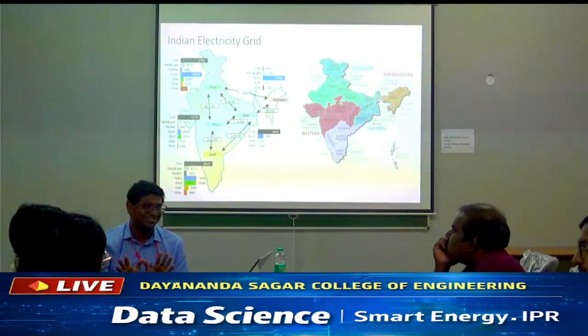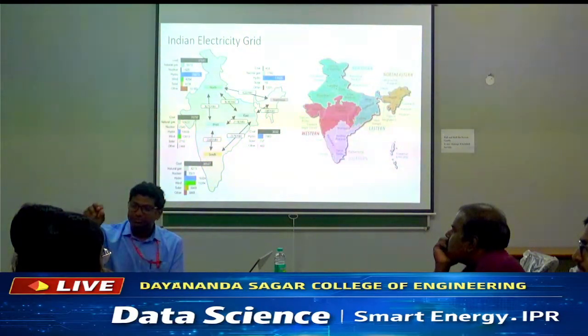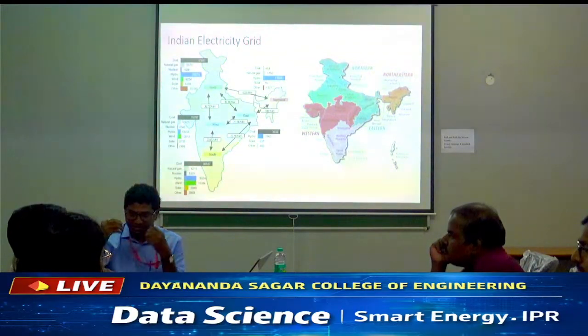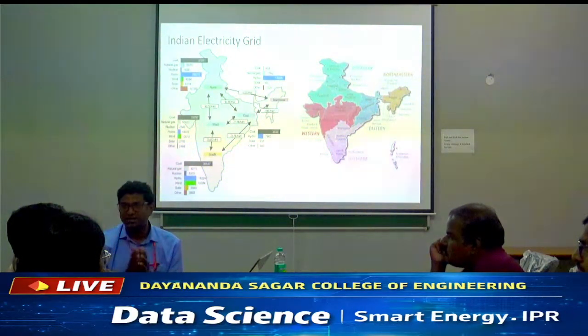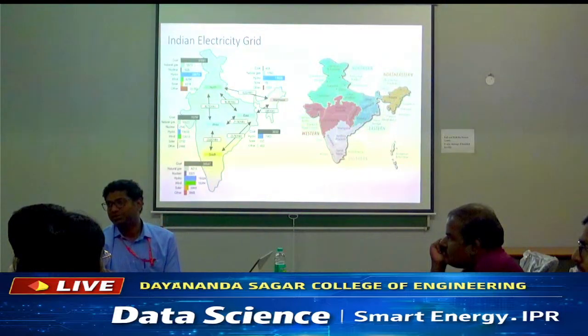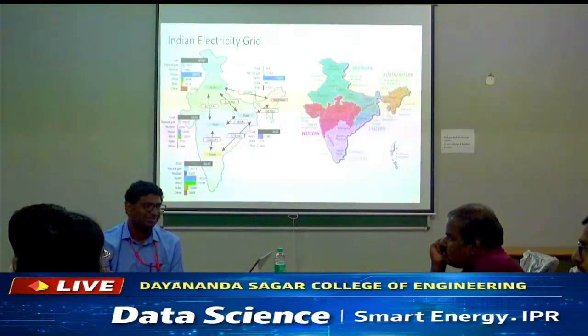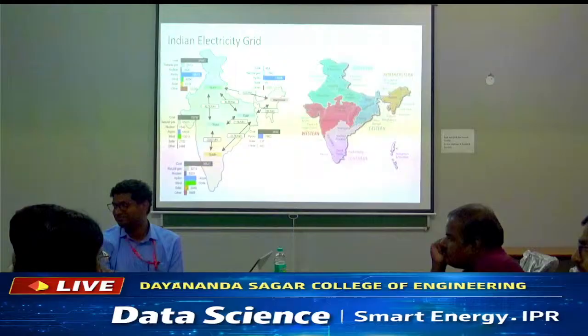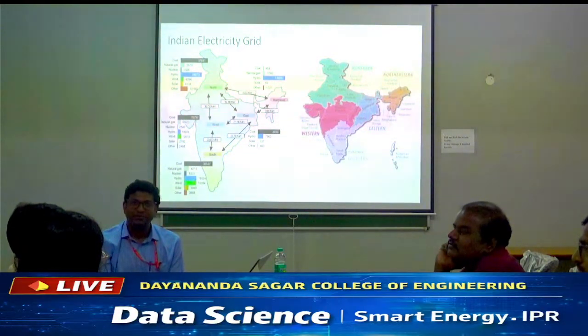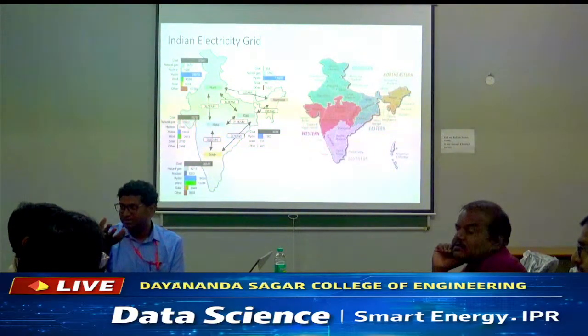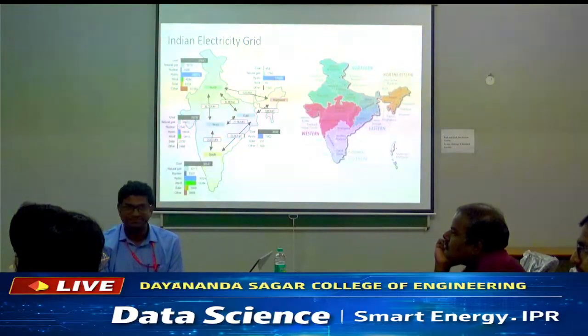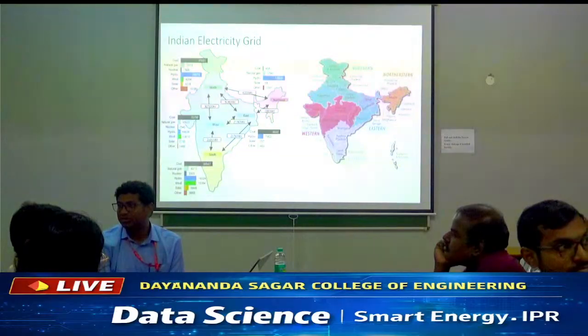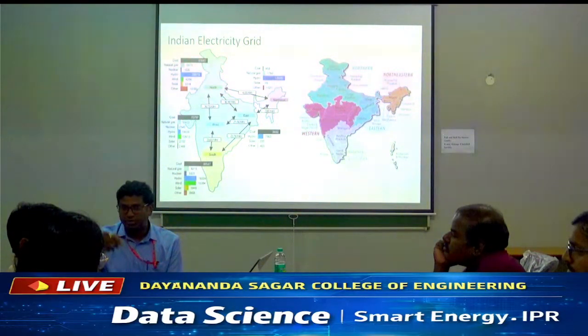Power cannot be pumped. Even if you simply connect to the grid, you cannot pump power from your system. Why? Because according to theory, the inverter cannot produce reactive power. But I also know that without reactive power, real power cannot flow. So if you have an inverter connected to the grid, can you pump the power? No, you cannot. For that, you need some amount of reactive power at the point of the inverter.